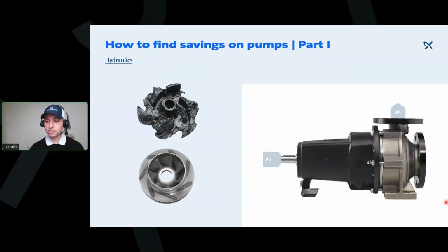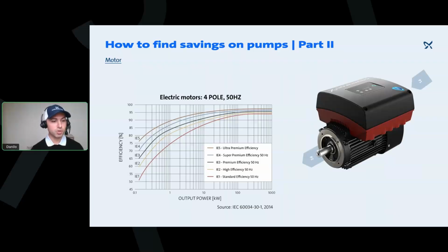And then what you can tell is this is very recent, right? We're in 2025 and we're only talking about 2020. So you can tell that many pumps that were manufactured prior to 2020 already have low hydraulic efficiency, right? So by just replacing an older pump with a newer pump, you can already find, I want to say, about 5% in energy savings here. Besides the hydraulics, right, all pumps, again, we're talking mostly centrifugal pumps, rotating equipment. Besides the hydraulics, that's when we come to motors, right? That's another good part of it.